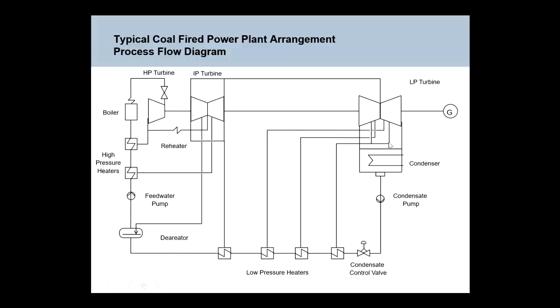And then as it's exhausted from the LP turbine, because you've got cooling water flowing through this condenser, the pressure at the exhaust of the turbine is subatmospheric. Okay, so inside the condenser, if you punch a hole in the side of the condenser, you won't get steam coming out, you'll get air rushing in, because the steam condensing causes a vacuum in that condenser. Does that make sense? Okay.